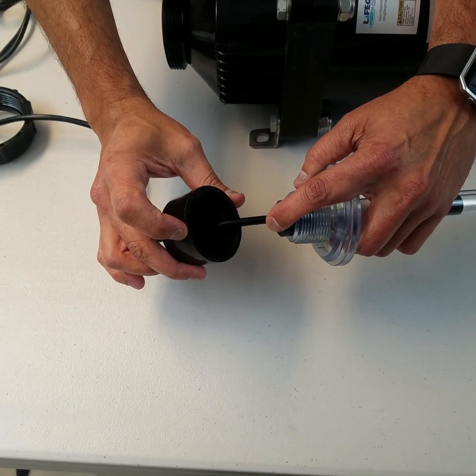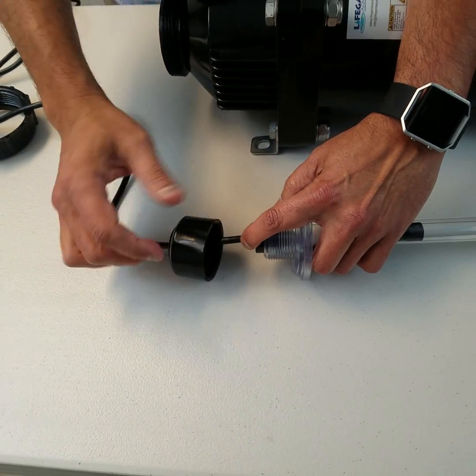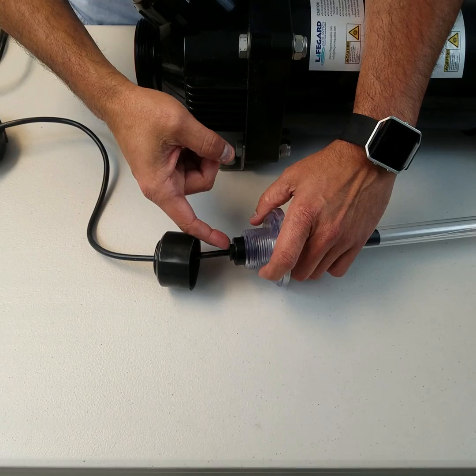You see, this is the part that seals and compression seals the quartz sleeve. This flattened end of the rubber will compress with the flattened end of this cap and it seals the quartz sleeve in place.